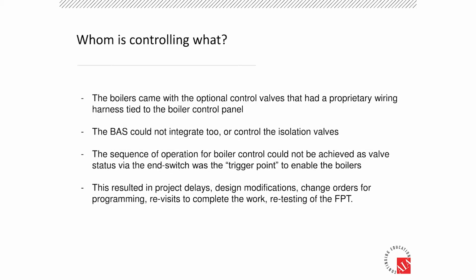We kept tripping off on high water temp. This was a high-profile building down in DC with some very high-profile banking executives, and people were screaming everywhere. So again, you do your boiler replacement projects in the summer, things were starting to get delayed. We were starting to get into that heating season, and we couldn't get the boilers to run. So we couldn't integrate. The end result ended up being increased project delays. We had to do some design modifications to modify the control sequence because the control contractor is not going to change anything until he's directed to. So we had some change orders there, revisits to the site by the entire project team, and retesting of the functional performance testing with the commissioning agent on site there.